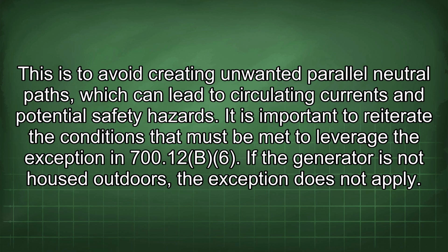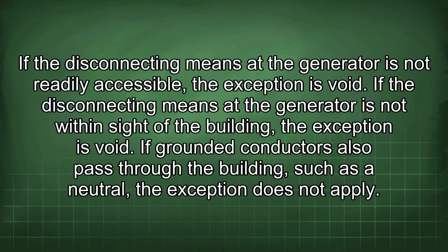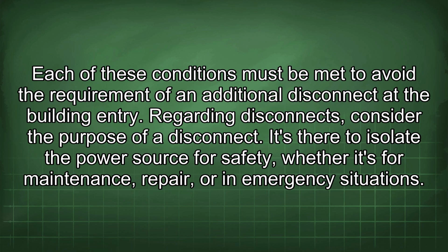It is important to reiterate the conditions that must be met to leverage the exception in 700.12(B)(6). If the generator is not housed outdoors, the exception does not apply. If the disconnecting means for the generator is not readily accessible, the exception is void. If the disconnecting means for the generator is not within sight of the building, the exception is void. If grounded conductors also pass through the building, such as a neutral, the exception does not apply. Each of these conditions must be met to avoid the requirement of an additional disconnect at the building entry.